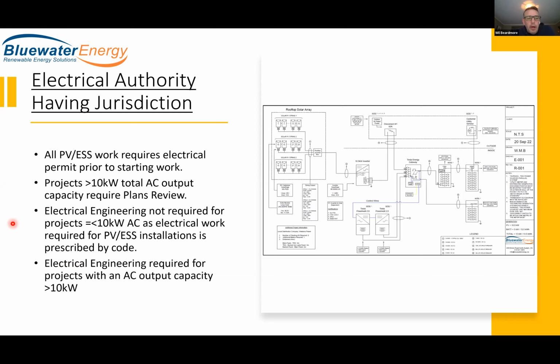Projects under 10 kilowatts AC do not require electrical engineering, as pretty much anything that we're doing is prescribed by code, and as long as the installation meets code, then we're fine. We do run into situations where electrical inspectors that don't have experience with PV systems and energy storage systems slow our progress down sometimes. We've had projects sit for a couple of months because the inspector didn't understand what we were doing. We had to go to technical advisors and move it up the chain of command so that we could get certification and closure on the project. So that does happen. We're trying to educate everybody as quickly as we can, but we do run into it from time to time. Electrical engineering is required for projects that are greater than 10 kilowatts.